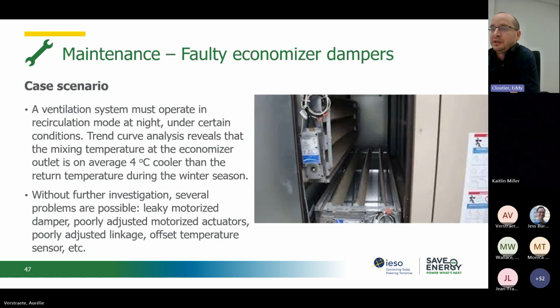Next case scenario would be a faulty economizer damper. In that case, this ventilation system must operate in recirculation mode at night. And trend curve analysis revealed that the mixed temperature at the economizer outlet is on average 4 degrees Celsius cooler than the return temperature in complete recirculation. So without further investigation, several problems are possible in that case. First, of course, a leaky motorized damper. It could also be a poorly adjusted motorized actuator or linkage, and also it could be a sensor that is offset.